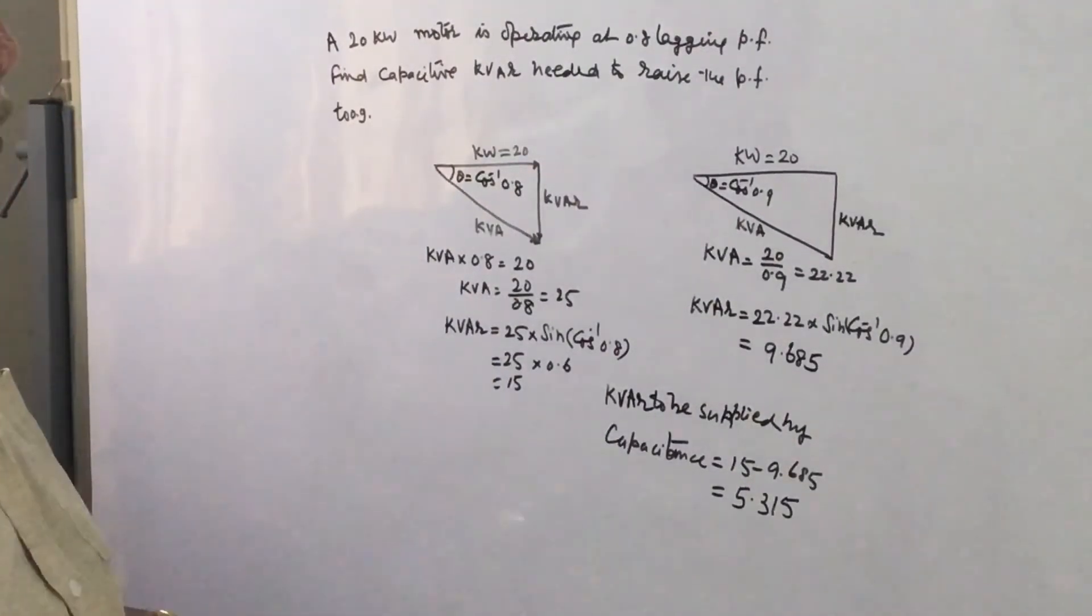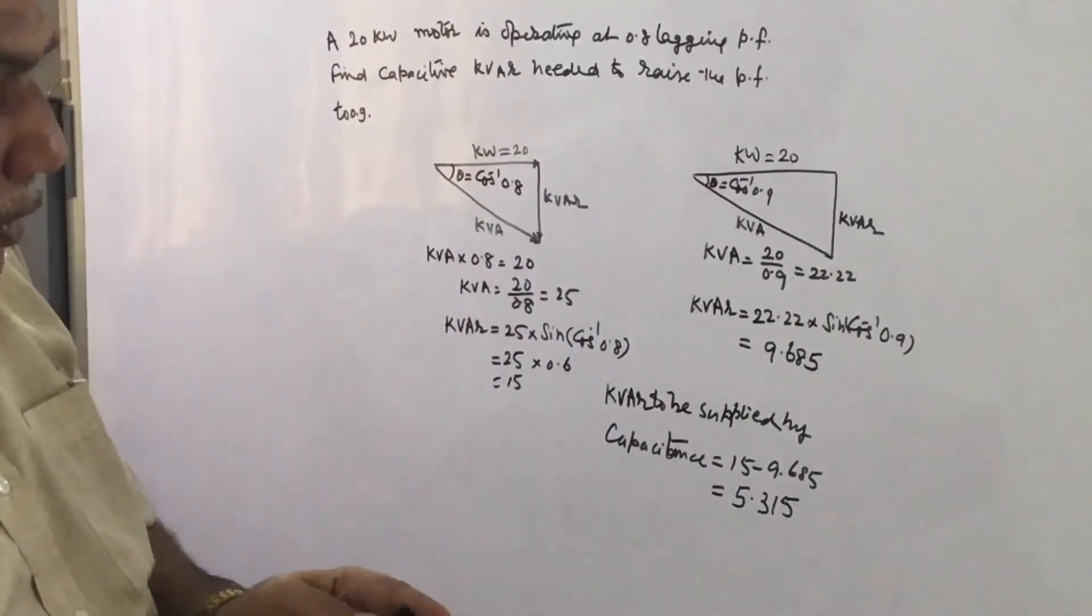So a capacitance having kVAR of 5.315 should be connected to raise the power factor to 0.9 from 0.8. This is how we can find out the kVAR requirement by using this power triangle.